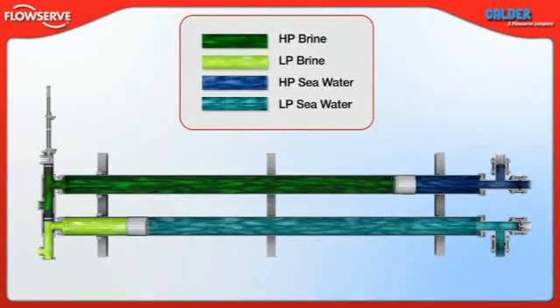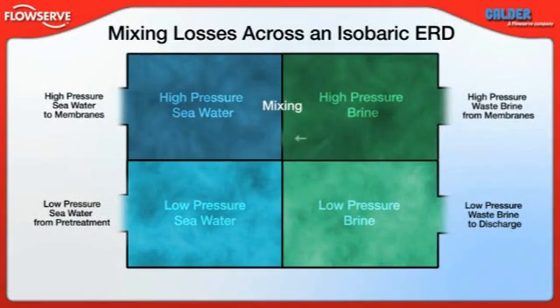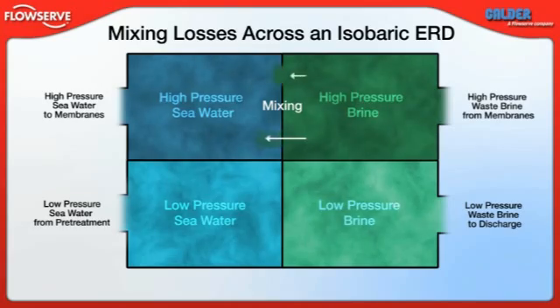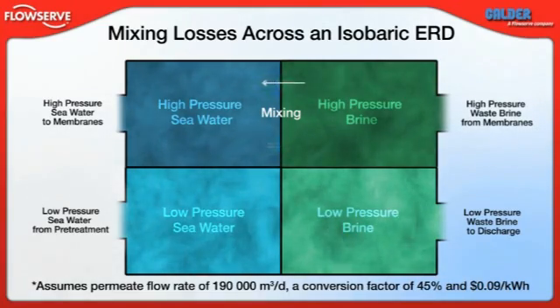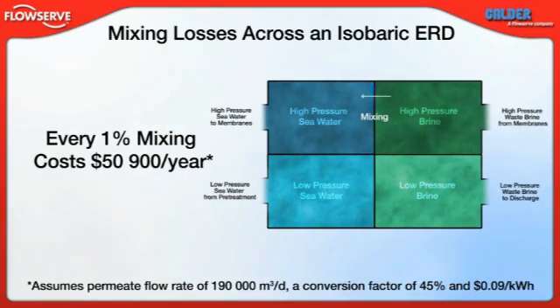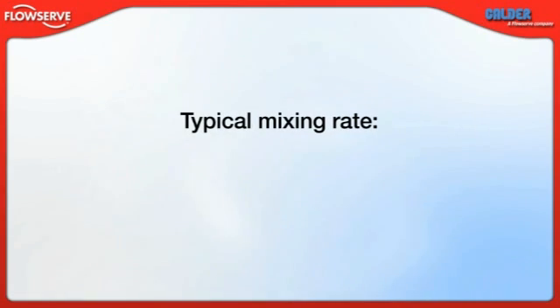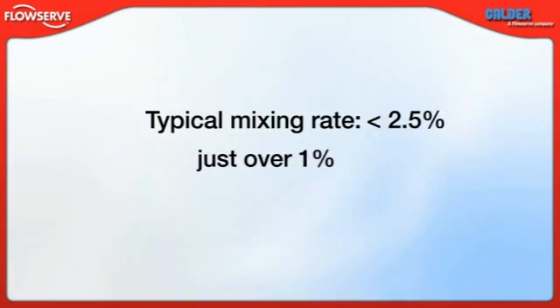The key to the DWEER's excellent performance is its extremely low mixing and leakage rates. Mixing refers to contamination of the sea water by the brine stream prior to the sea water entering the membranes. Because the required membrane feed pressure increases with salinity, a high mixing rate results in greater power consumption by the high pressure feed pumps. For a plant with a permeate flow rate of 190,000 cubic meters per day and a conversion factor of 45%, every 1% mixing over an isobaric ERD results in an additional $50,900 USD, assuming 9 cents per kilowatt. The typical mixing rate over a DWEER is less than 2.5% by volume, which results in slightly more than 1% mixing rate at the membrane inlet.